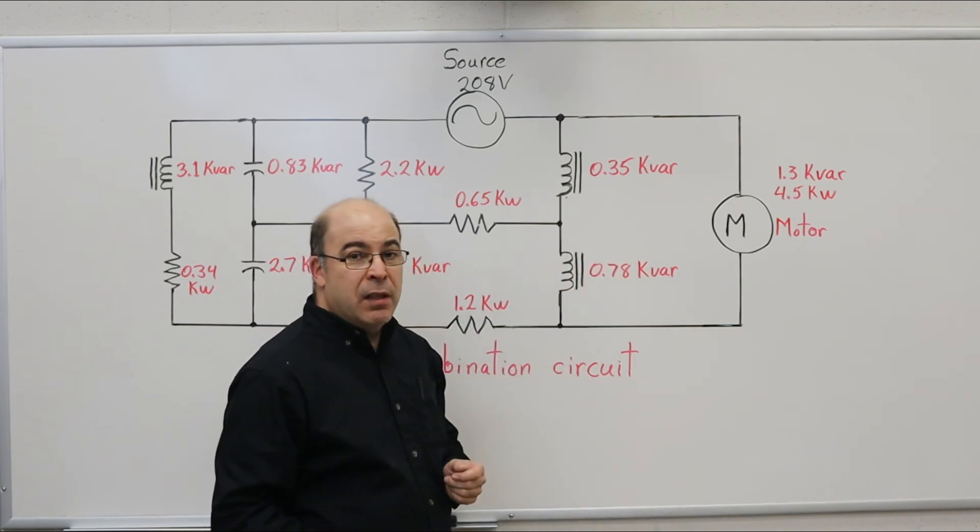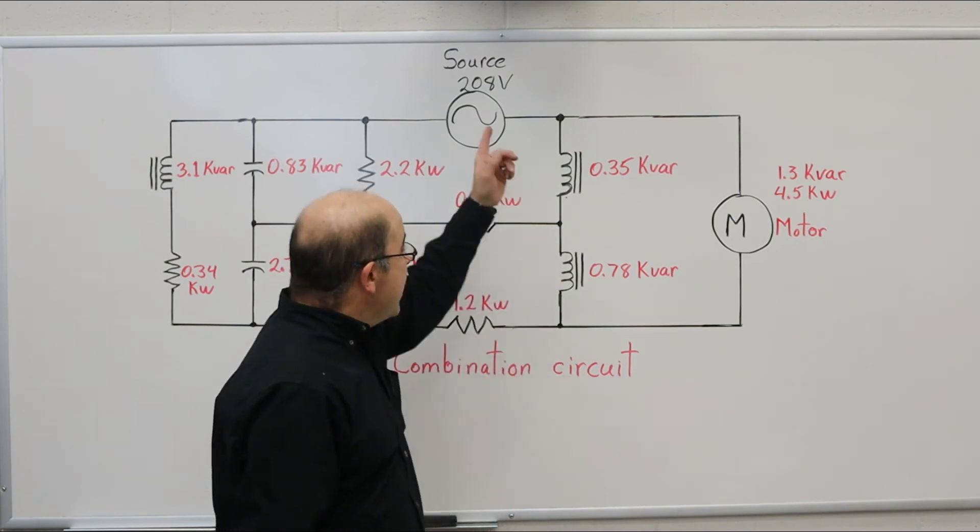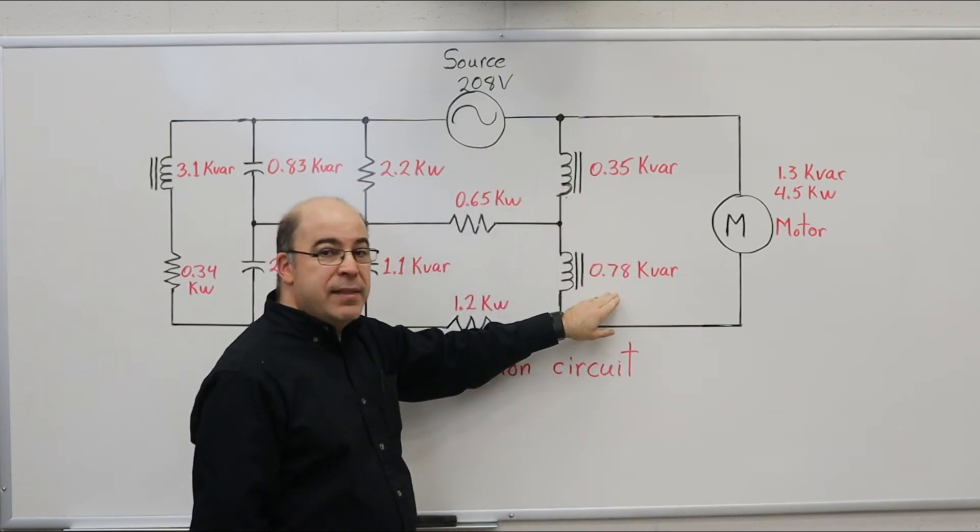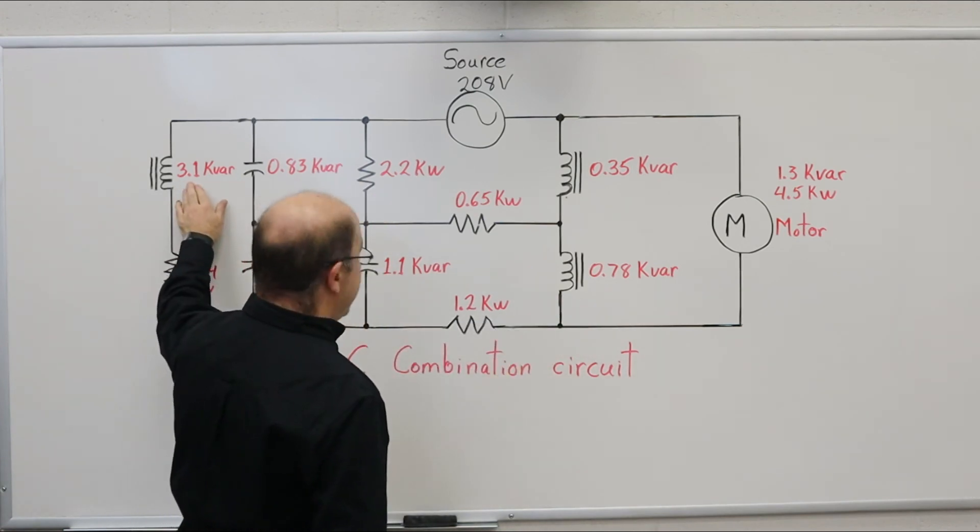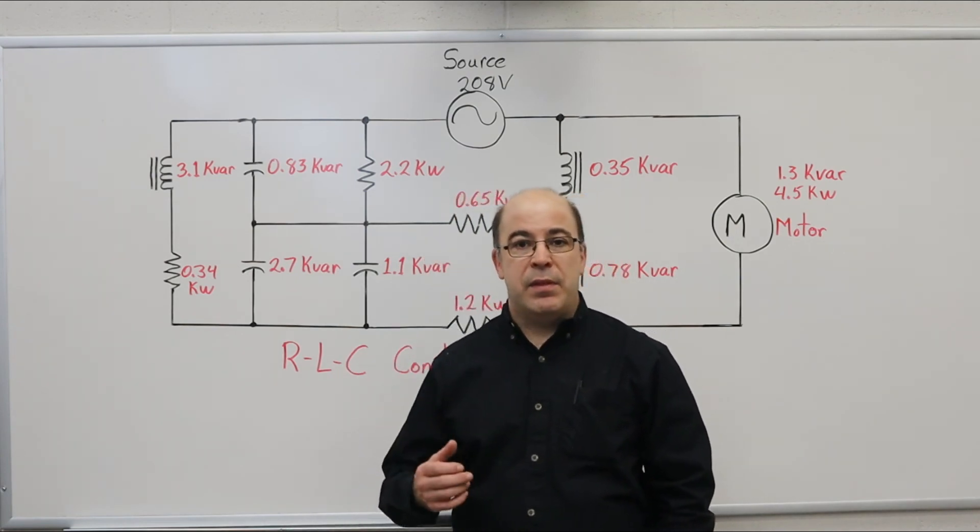the motor counts twice: once as a resistive load, the second time as an inductive load. So that 1.3 kVAR is going to be put into the inductive category, as well as these values: 0.35 kVAR, 0.78 kVAR, and 3.1 kVAR. We're going to add those together.